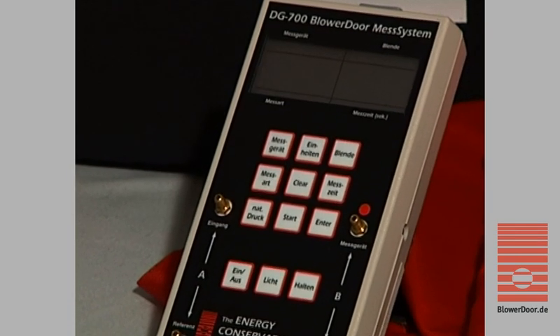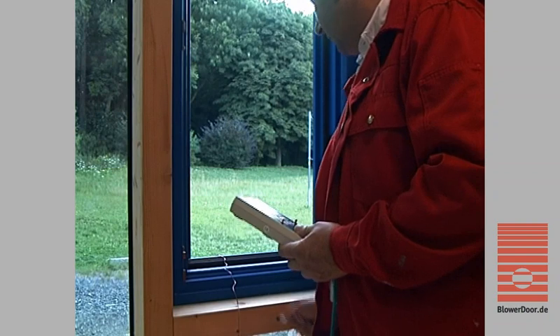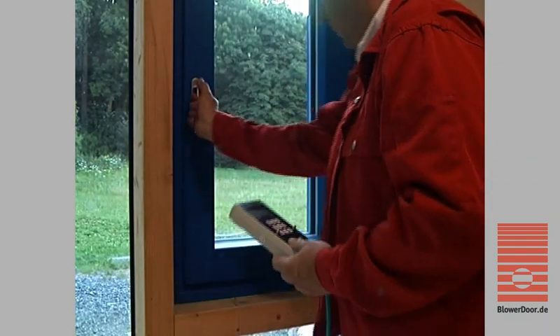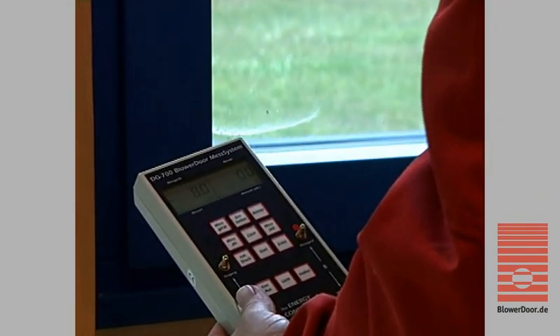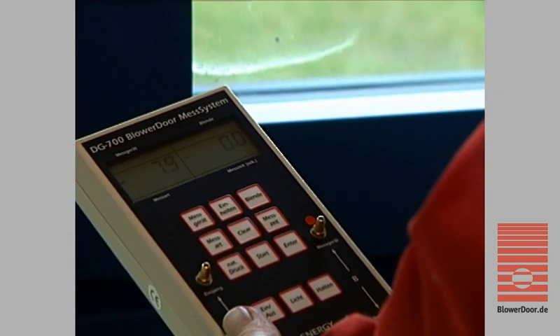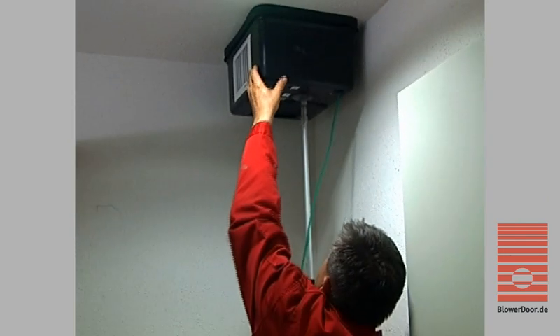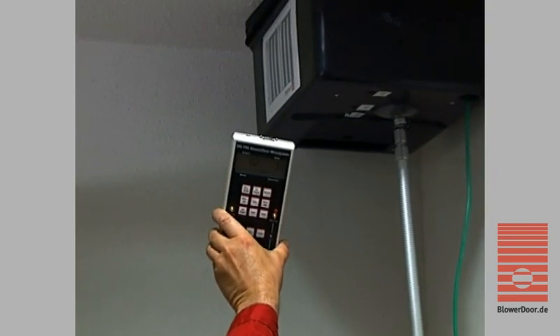The versatile DG700 Digital Pressure Gauge can also be used as a handheld instrument for testing the performance of ventilation or air conditioning systems. Using a tube allows a pressure connection to the outside. The ventilation system with heat recovery should create zero Pascal pressure difference between the inside and the outside — this is quickly verified with a DG700. The exhaust fan flow metering box is used to measure air flows at exhaust air valves.